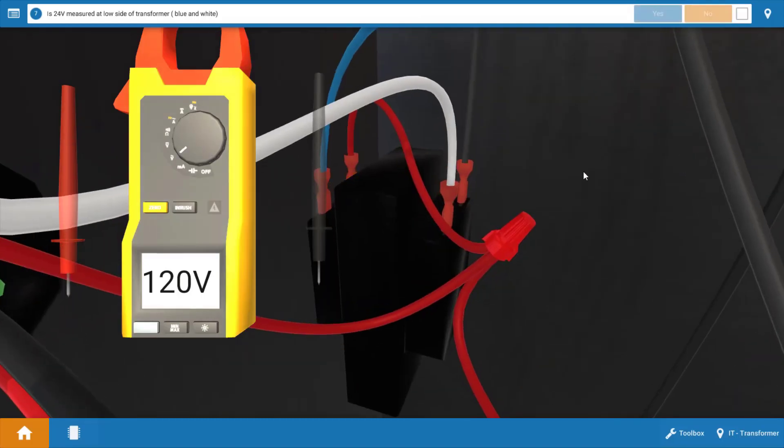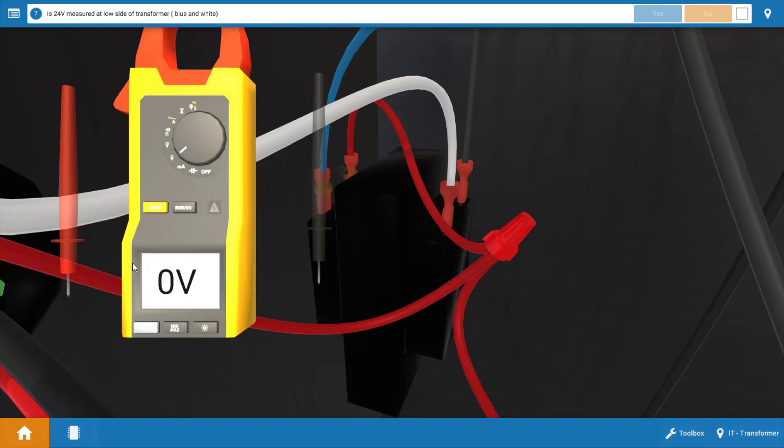Our next step is to check for 24 volts at the transformer secondary. So we're going to place each of our leads across the glowing orange hot spots at the transformer secondary here at the blue and white wires and we see we have zero volts here.